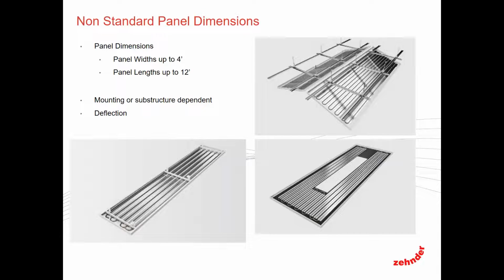Non-standard panel sizes, all the way up to a 4-foot width and then a 12-foot in length. Now, the disclaimer I'm going to say on this is those are very dependent upon your substructure and the type of ceiling you're putting these in. So generally, if you're going to lay a panel in a standard lay-in grid, tegular or standard 15/16 grid, you really don't want to go anything over, say, 30-inch width and 10 foot in length, because the deflection across the face of the panel as it heats up and cools down will start pulling up out of the grid and you'll see changes. It won't lay flat.